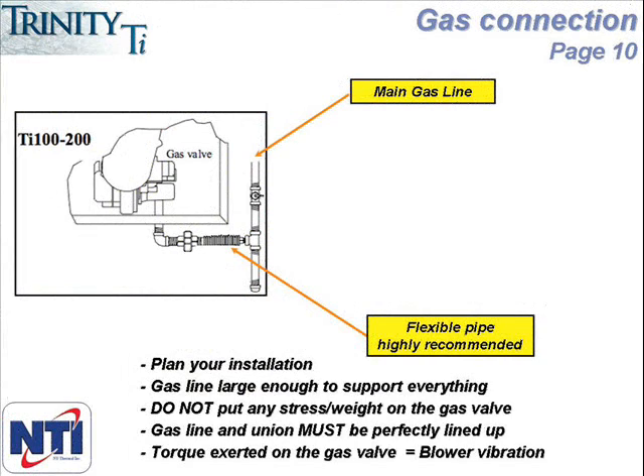When installing the gas line, the line enters the boiler at the bottom of the cabinet. Your main line should include a shutoff valve with a T-type handle that needs to be listed with a nationally recognized testing lab. You should also include a drip leg, and ideally the section between the main pipe and the union should use flexible gas pipe, provided local codes allow it.